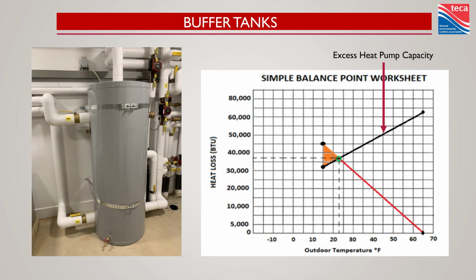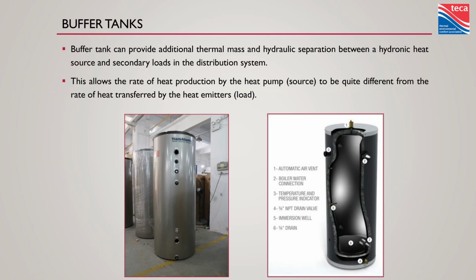It's a tank. There's lots of them on the market. They're insulated, but if you're running chilled water through it, make sure it has some vapor-sealed insulation. We don't want that tank to start sweating with the chilled water in it. It's going to rust. It's going to fail. I've seen them die in less than 2 years. So make sure you're picking the right kind of buffer tank if you're doing heating and cooling with these systems.